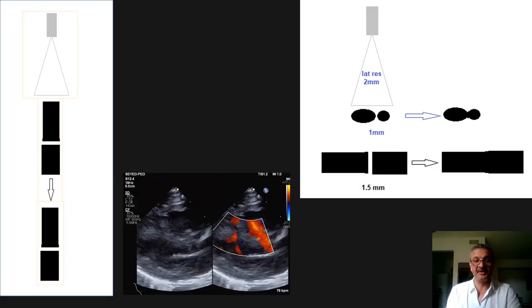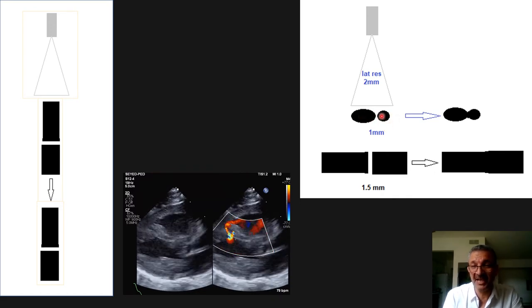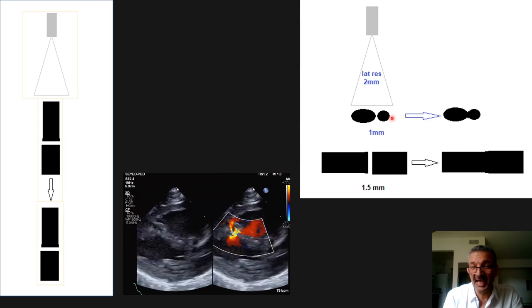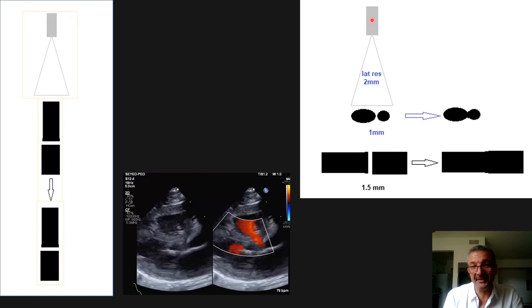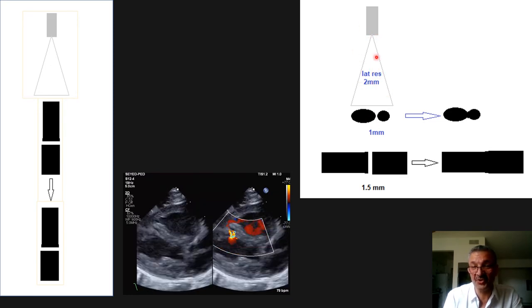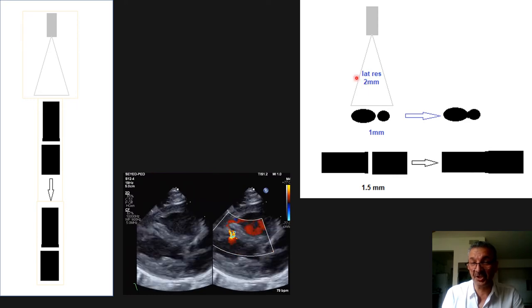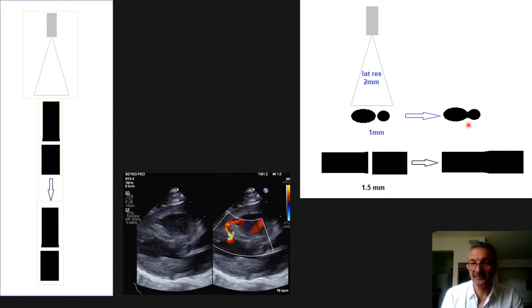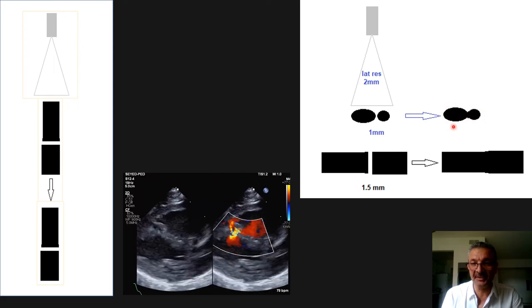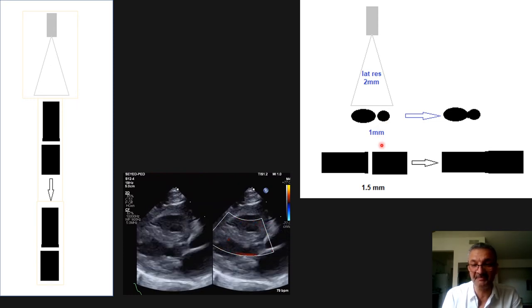On this schematic, imagine we are scanning two particles of different shapes that are separated by 1 millimeter and lined up perpendicular to the sound wave. Since the best machine has a lateral resolution of about 2 millimeters, and the distance between them is less than that, the machine shows them as one entity — not as two separate particles — even though in reality they are 1 millimeter apart.